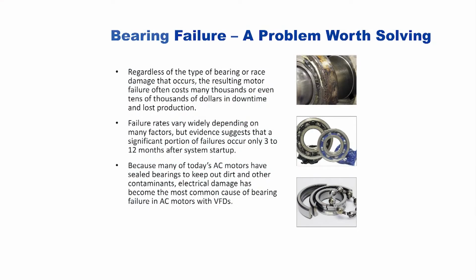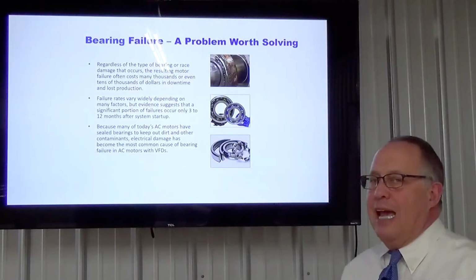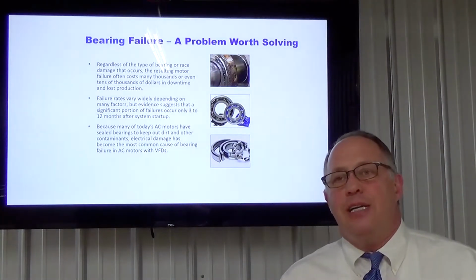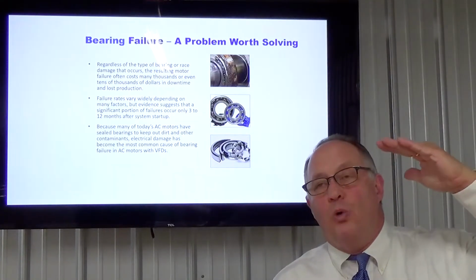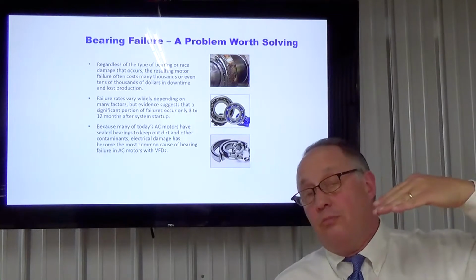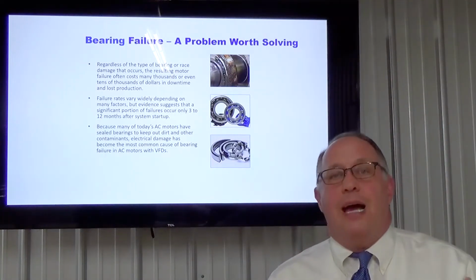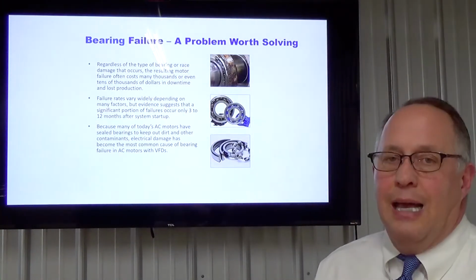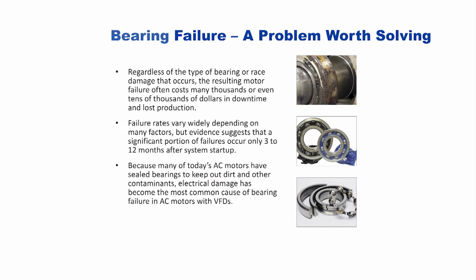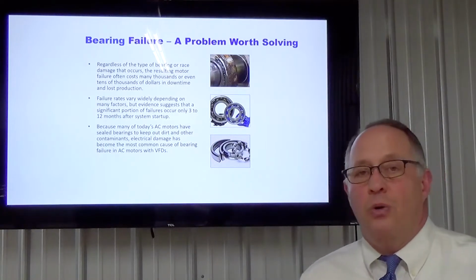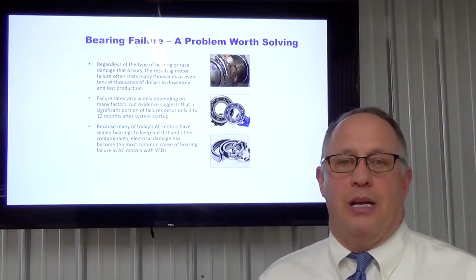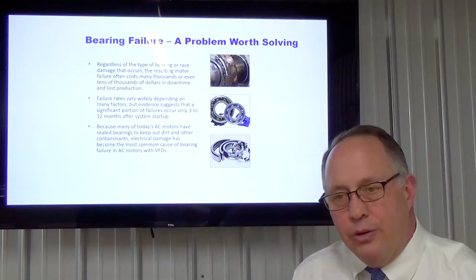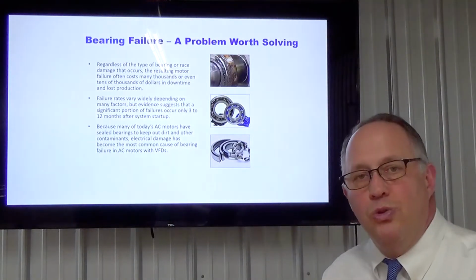Failure rates can vary on many factors, some of the ones we discussed, but evidence suggests that a significant portion of failures occur only 3 to 12 months after a startup. I have seen this as well. If it's intense enough, if it develops a voltage wave arc that's 20 volts and higher, then you've got less than 12 months before you end up with a bearing failure as a result of motor failure. Because today's AC motors have sealed bearings to keep out dirt and other contaminants, the electrical damage has become the most common cause of bearing failure in AC motors with VFDs. Remember, I said some estimates have it as high as 90% of all motor failures. They're bearing failures, but those bearings seize and cause you to lose your motor.